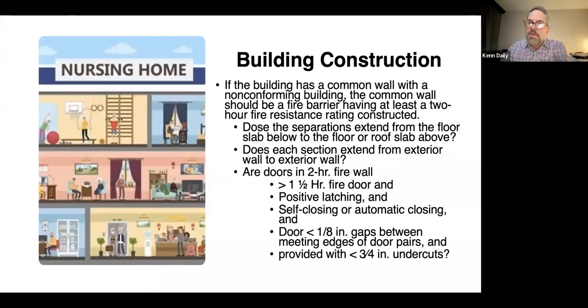The number one issue, and I know many of you would have this, is where you have your nursing facility, again, conforming space, separate from personal care homes, or maybe called assisted living, residential care, independent living, or other types, even office space. So it's separated by a 2-hour wall. And then within that 2-hour wall, hopefully you don't have any penetrations. You have to seal those appropriately, but then you have a 90-minute door, which has to be inspected, tested, and maintained. Of course, it has to close and latch, has to have positive latching hardware. Every once in a while I see where the door does not have that. And there's the issue of gaps, undercut, all of that. But that's really the most common, K161.